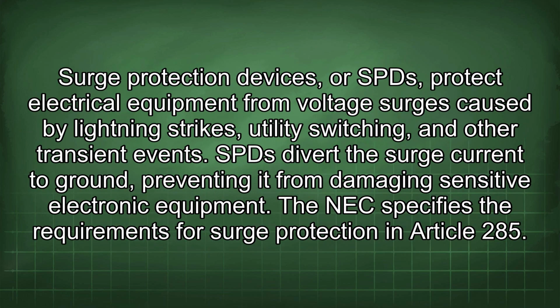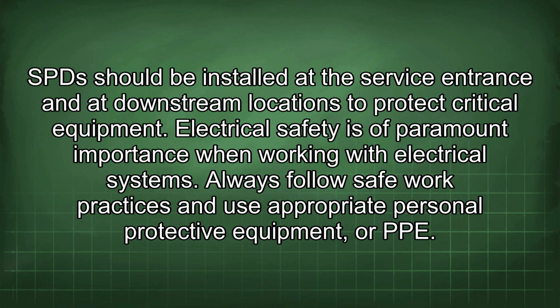Surge protection devices, or SPDs, protect electrical equipment from voltage surges caused by lightning strikes, utility switching, and other transient events. SPDs divert the surge current to ground, preventing it from damaging sensitive electronic equipment. The NEC specifies the requirements for surge protection in Article 285. SPDs should be installed at the service entrance and at downstream locations to protect critical equipment.